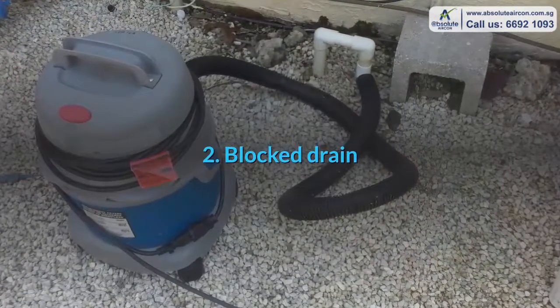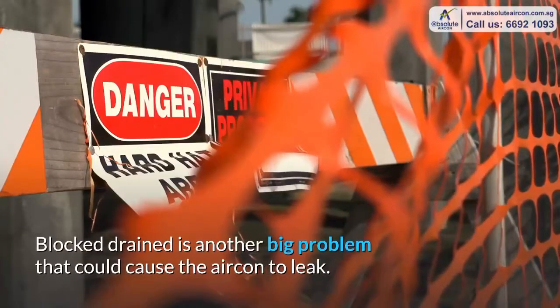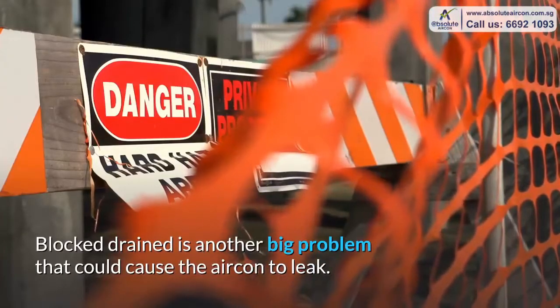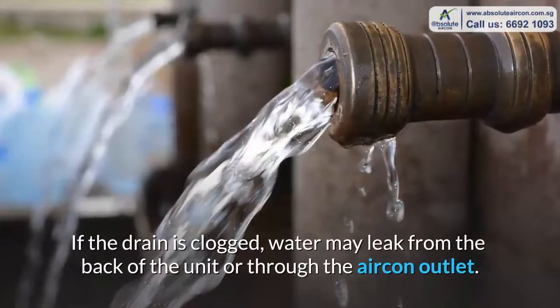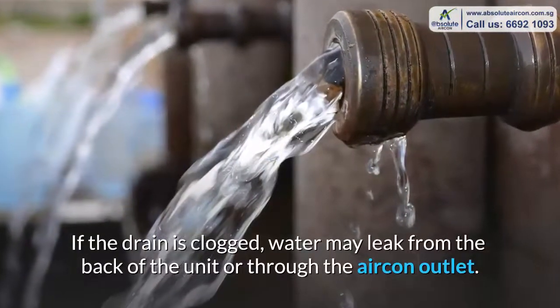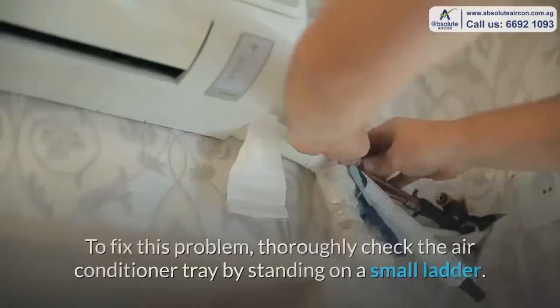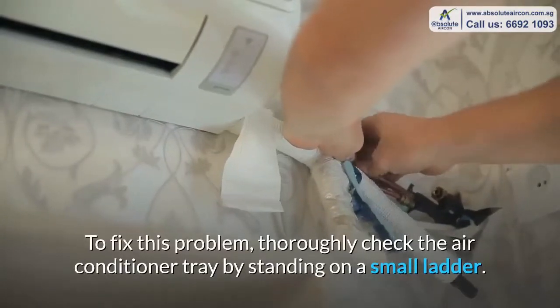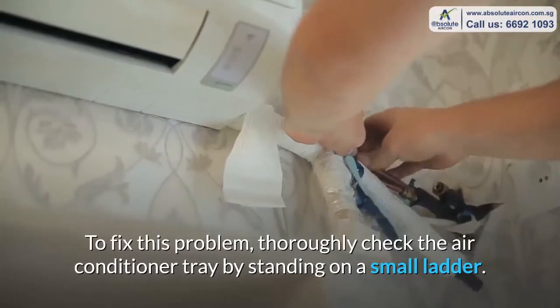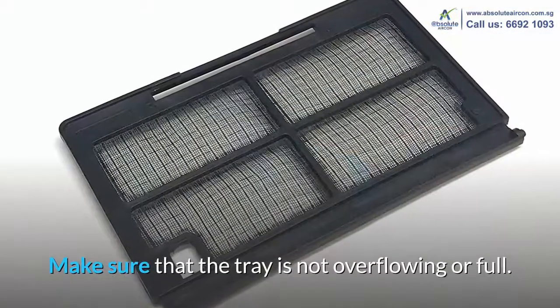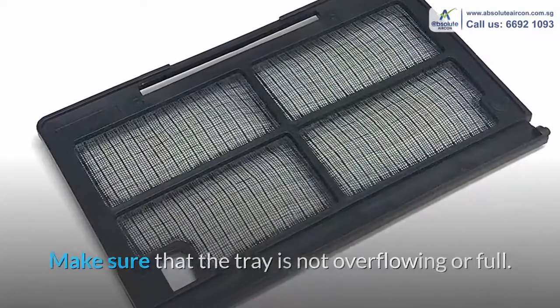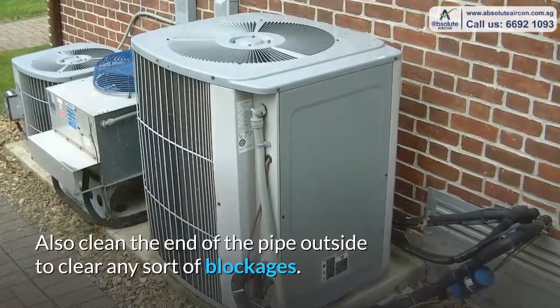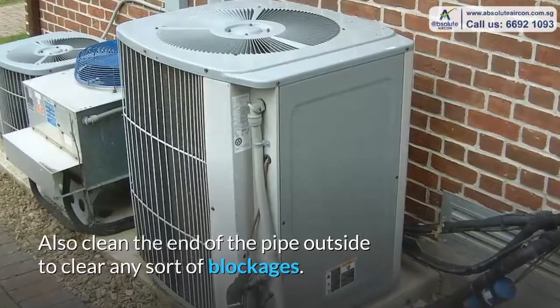2. Blocked drain. Blocked drain is another big problem that could cause the aircon to leak. If the drain is clogged, water may leak from the back of the unit or through the aircon outlet. To fix this problem, thoroughly check the air conditioner tray by standing on a small ladder. Make sure that the tray is not overflowing or full. Also clean the end of the pipe outside to clear any sort of blockages.